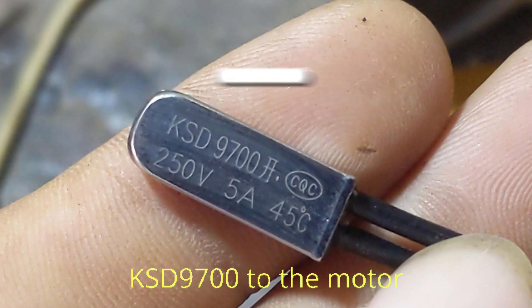Disconnect power: ensure the motor is disconnected from the power supply before installation. Mount the switch: attach the KSD 9700 to the motor housing or a suitable heat sink to ensure it accurately senses the motor's temperature.